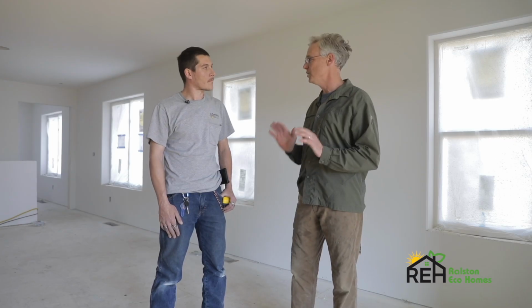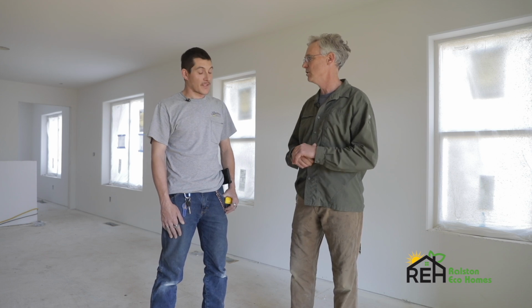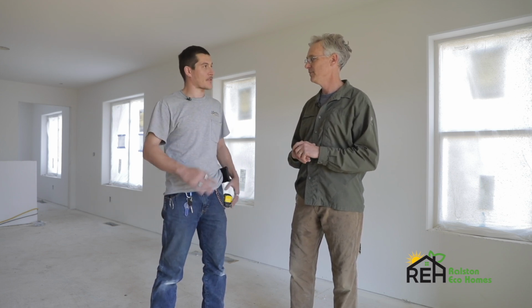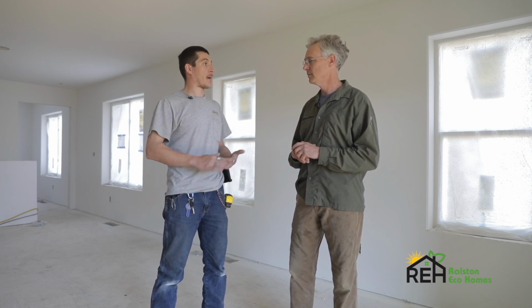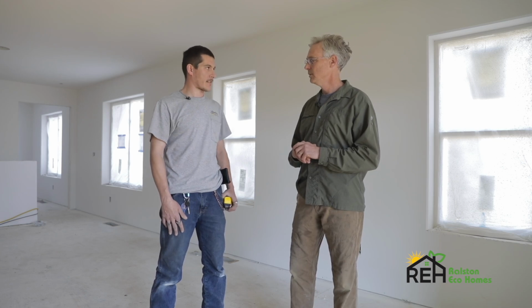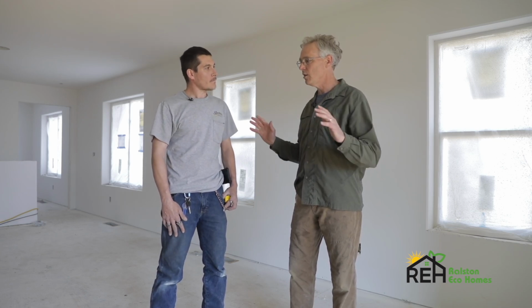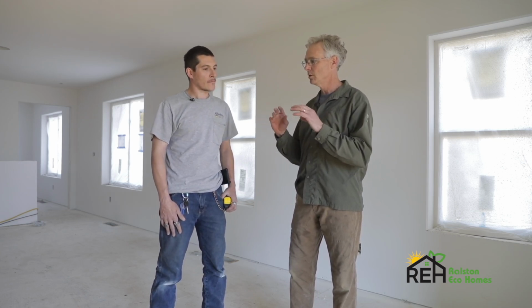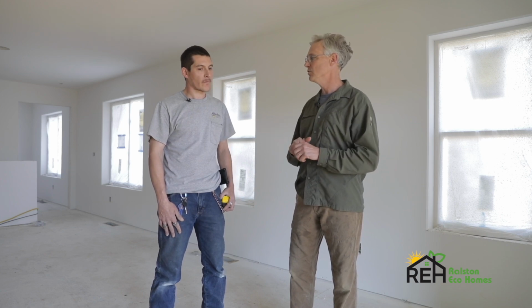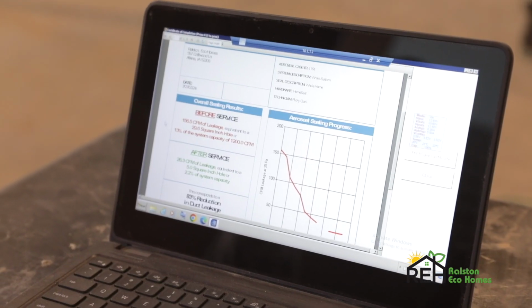So where did this house start for its leakage? So this actually started out right about that 6% that we wanted that would be considered passing. So it's right around 156 CFM. So if we looked at the entire amount of the ductwork, there's a 6% leakage from it, which, if I remember correctly, was about a 30 square inch hole. Yes. Okay. And then you took about 10 minutes, roughly, to seal it, which is quick.